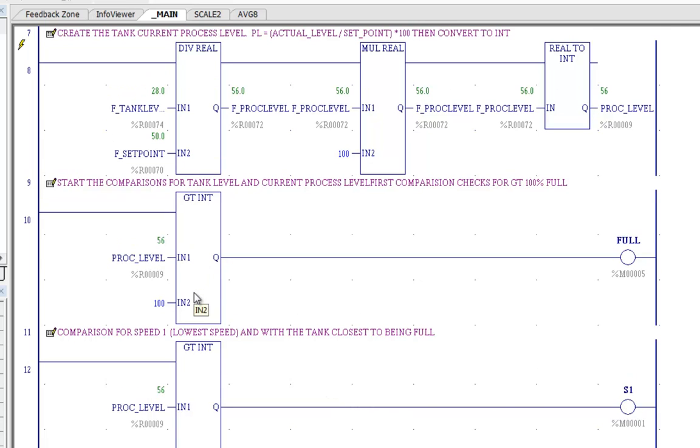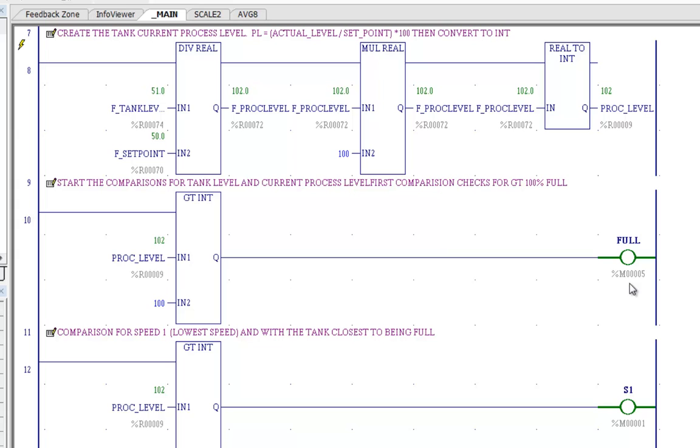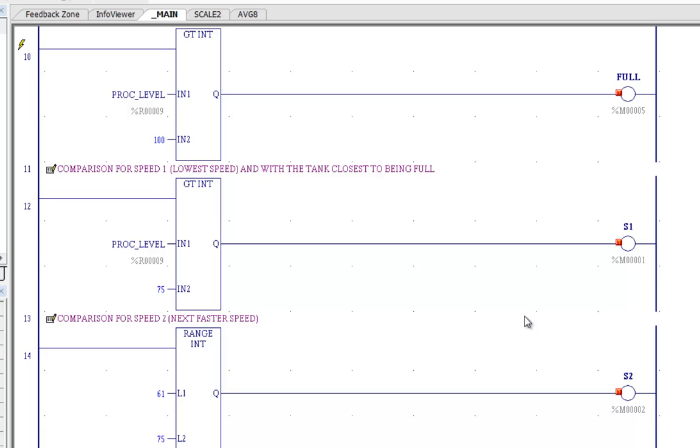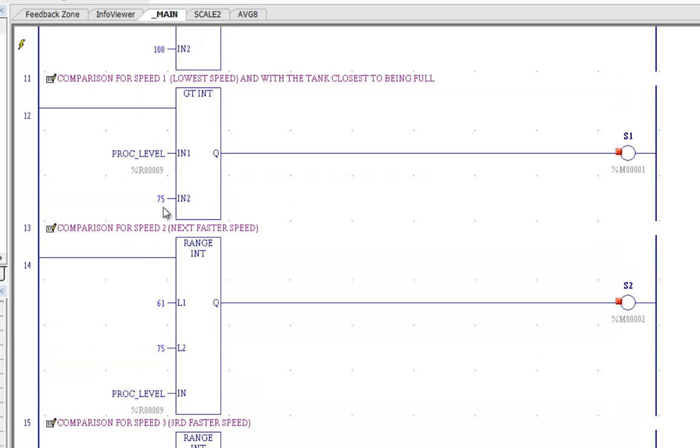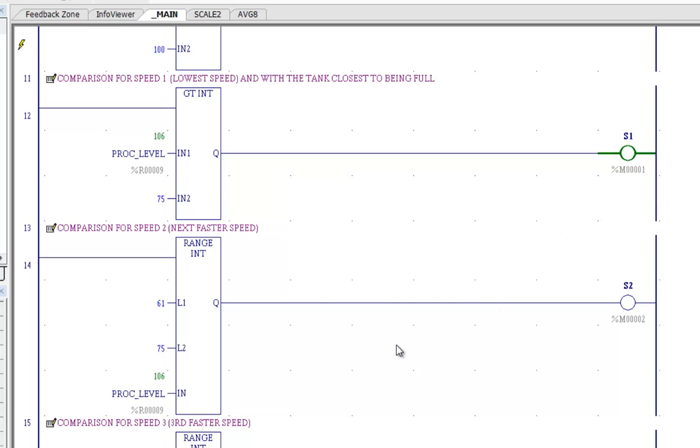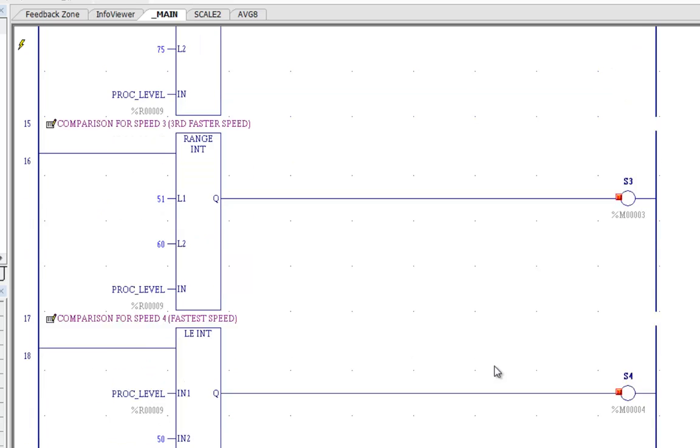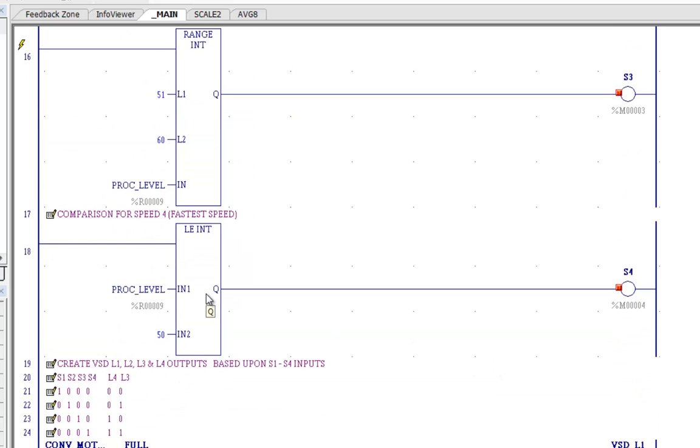And if we look here, if our process level is greater than 100%, watch this. Now we're 102% full. Our tank full goes on and everything else should stop at that point. Now we're going to compare our process level for between 75 and 100. There's our slowest speed. If we bring this down between 61 and 75, there's our next speed. We bring it down even lower, we've got our third to the fastest speed. And then finally, we've got our highest speed.